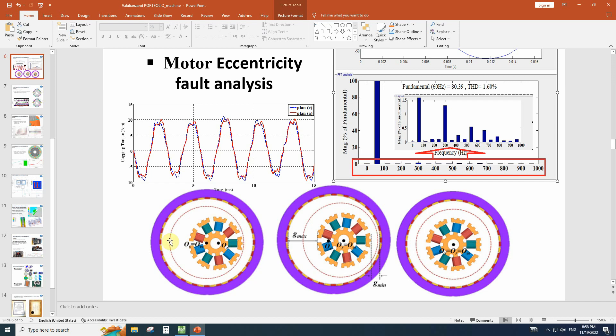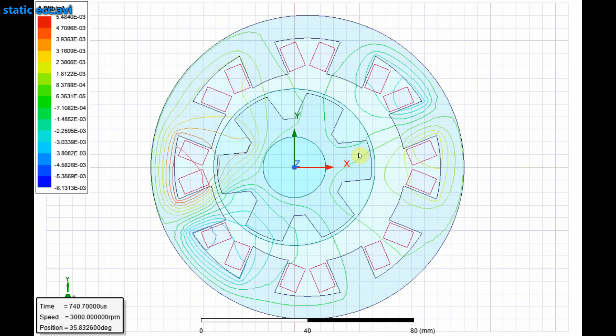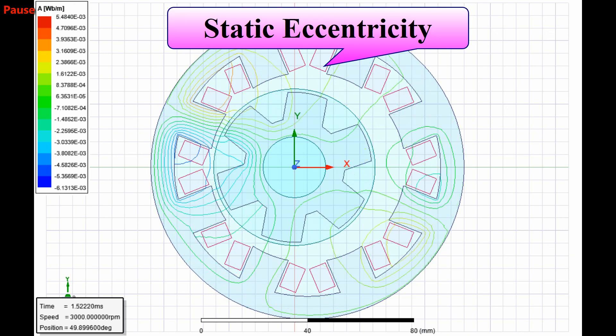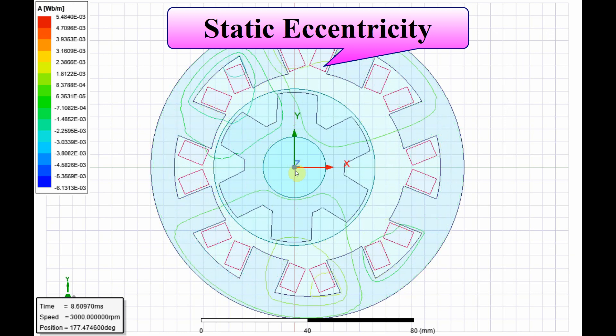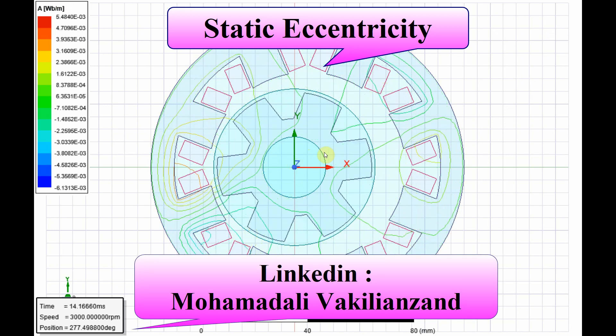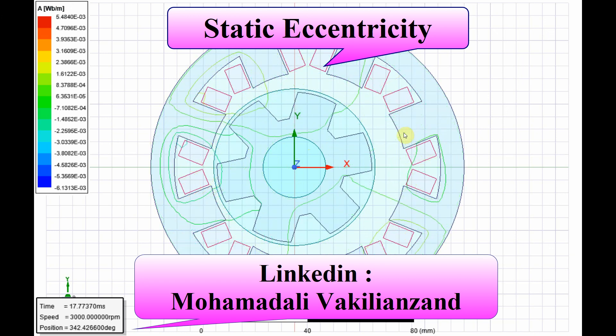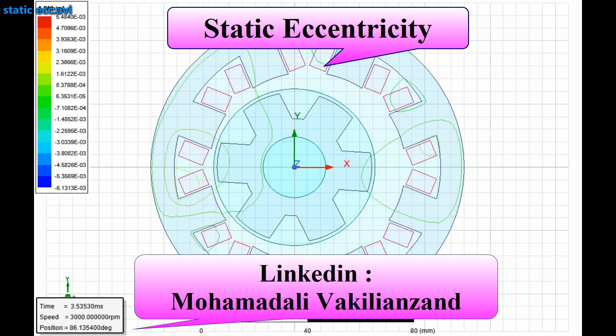To show these two faults better, I made a video on each one of them. It is an SRM motor with an exaggerated air gap. In a low air gap distance, we can't see what's happening there, but in this simulation we will have a big air gap machine to understand the problem better. In this animation, you can see the static eccentricity — the rotation center is matched with the rotor center and the stator has displacement.